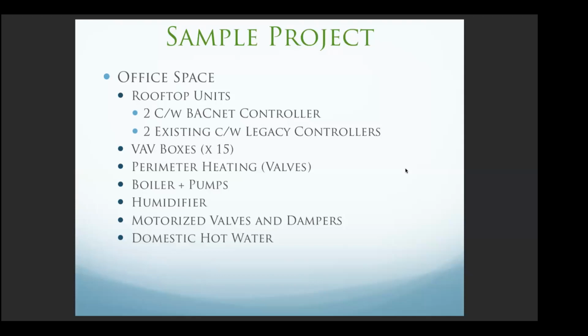I mean, here's the thing. In an MSTP-based system, you have the physical link going from controller to controller to controller. In an IP-based system, you don't have that one link per se, but now you need to get IT involved so we can have Ethernet drops, or sometimes depending on how the job goes, it may come in your scope. But basically, IT will be heavily involved because their system is going to get super clogged by all the data that is flowing through. Now, when I say super clogged, it's not to a point where they can't do anything. It's just a lot more data than they're normally used to seeing, because now the BAS data is also on the same building LAN. So it's more from that perspective on how the IT department perceives it as well.